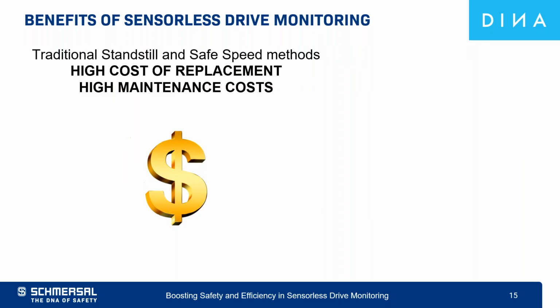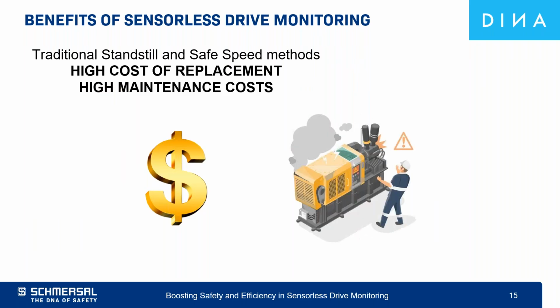Using redundant standard encoders requires having expensive devices out in the field to monitor a hazardous motion, as well as having expensive spare parts in stock, because if they're damaged, it usually leaves the machine in a stop status until it's fixed. As well, technology has changed throughout the years, and I've personally seen customers try to replace encoders without any luck, as the same model doesn't exist anymore, or they just plain old become hard to obtain.